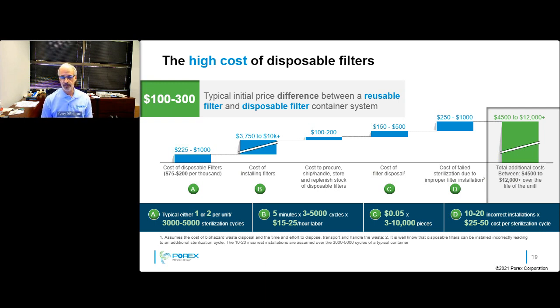Cost to install the filters. This is an absolute hidden cost that nobody really thinks about. But these products do have to be changed out. Somebody has to handle them. Certainly, there's always a risk of damaging the containers as they become handled and the filters replaced. But if you look at 5 minutes to replace each filter at 3,000 to 5,000 cycles, and if you're paying the average hospital labor $15 to $25 an hour, that can add up to $3,750 to over $10,000 in savings by not having that expense of replacing the filter.